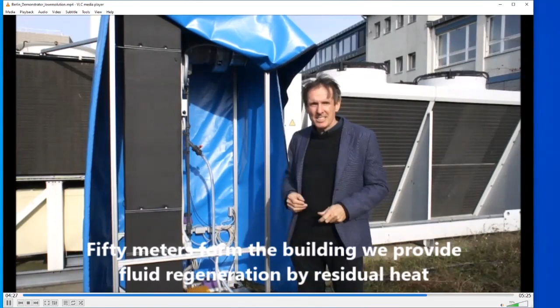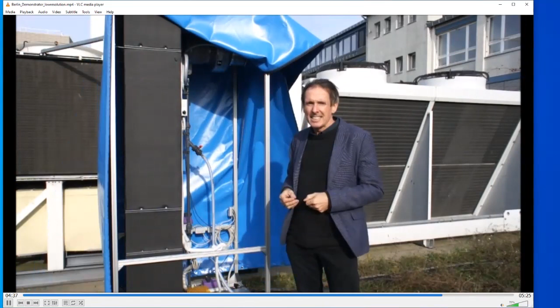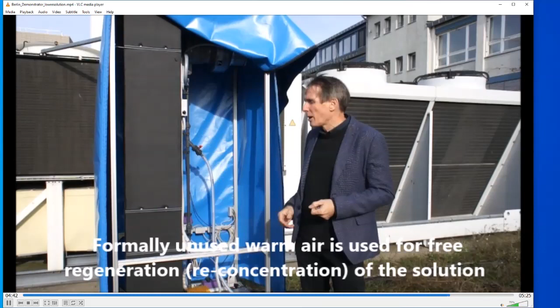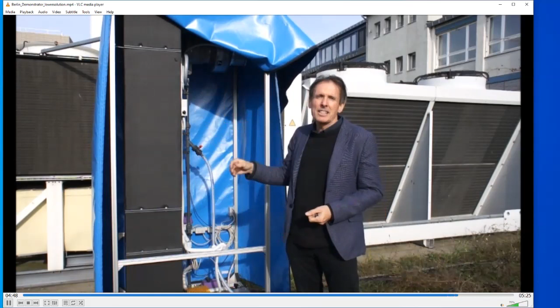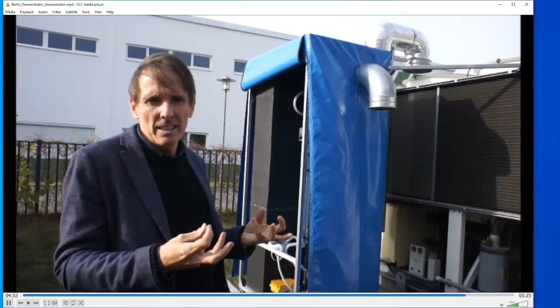Here we are at the regeneration unit of the system. Behind you see the residual heat device - we capture hot air coming from a cooling process, from machine cooling, which is normally unused, and bring it through our desorber. That means we have some heat in the air, which gets in contact with our thermochemical fluid. The water in the solution is evaporated and goes out through this tube, reconcentrating the solution, which is our energy carrier, and we collect it here in the tank.